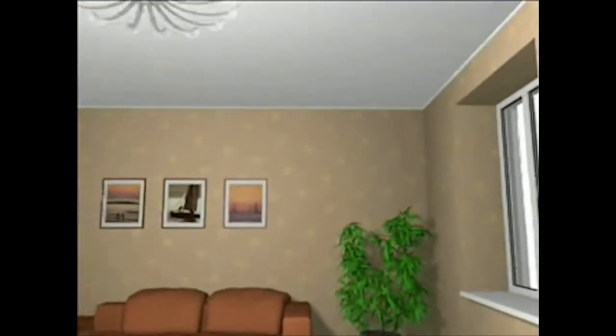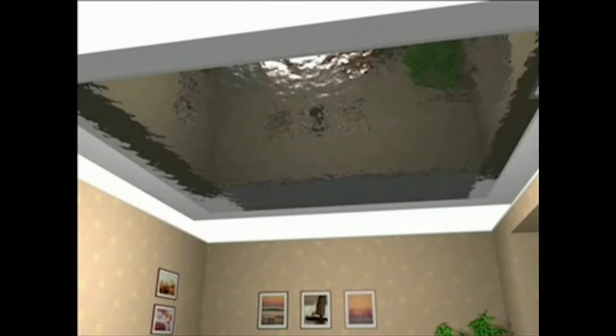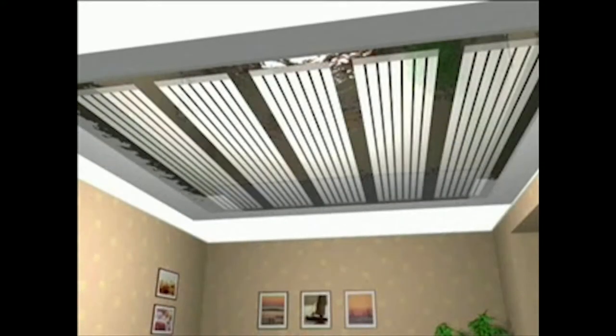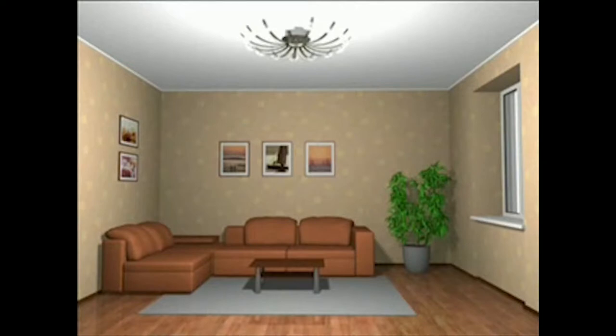Let's have a better look at the heating system. Thermal insulation and aluminum foil laminated film PLAN is installed on the ceiling with the help of a standard fitting mechanism. Installation covers 100% of the ceiling, while PLAN covers only 80%. After the setup is installed, it can be covered by any finishing material except metal sheets. The only visible part of the heating system will be the thermostat, which will be installed on the wall.